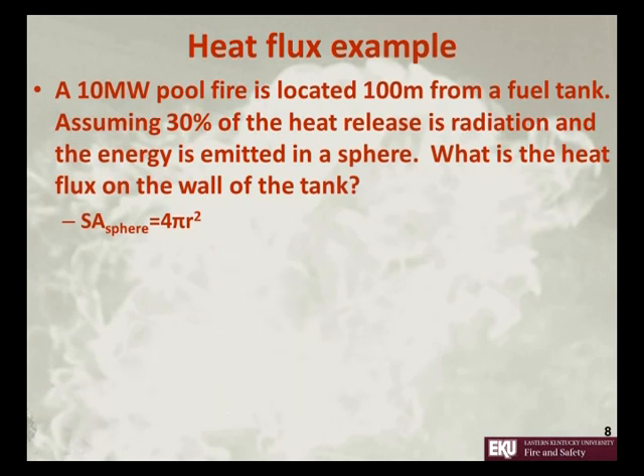We can solve our equation. We want to know the heat flux, q dot double prime, radiated at the tank. This is equal to our heat release rate times 0.3 divided by the surface area of the sphere, which is 4 pi r squared.